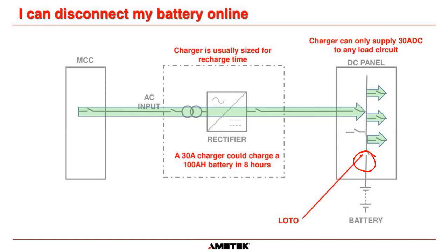Because like I said, the most common thing is everybody's got to conform to IEEE standards for their battery capacity tests. And if you're a NERC related plant, you have to do your battery capacity tests at a 3 to 5 year period. So somebody has to come in and disconnect the battery and do the test. And a lot of people will say, well, just for ease, we'll just open the battery disconnect and leave the charger supplying the loads. Don't do that. Get the battery company to temp in a battery for you and make sure that battery is sized correctly to match the battery that they're testing.